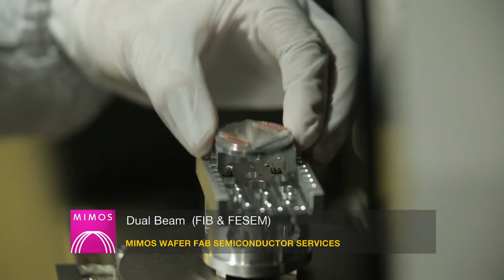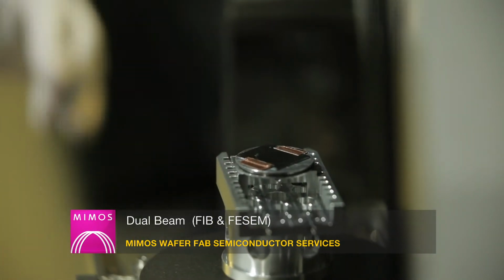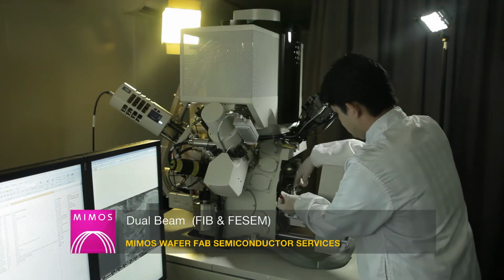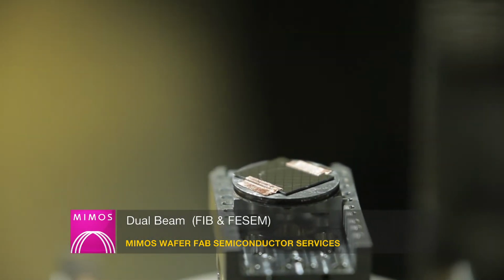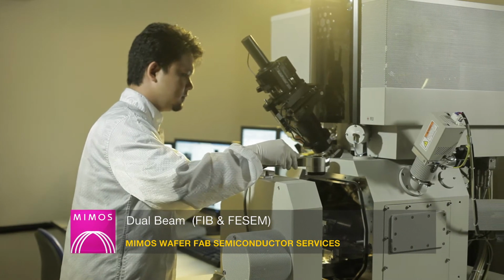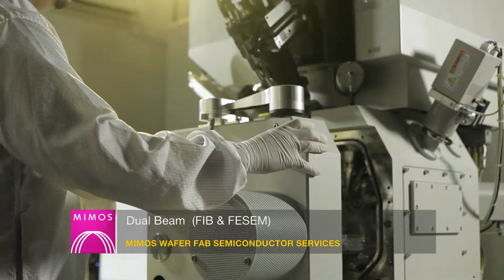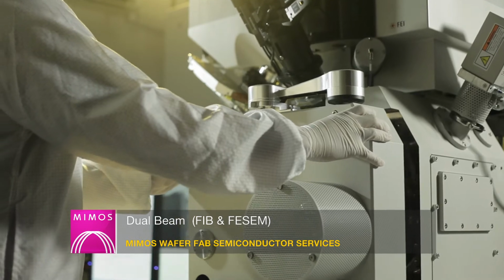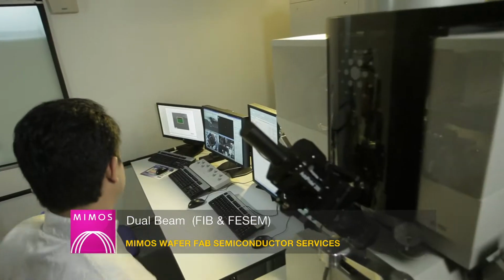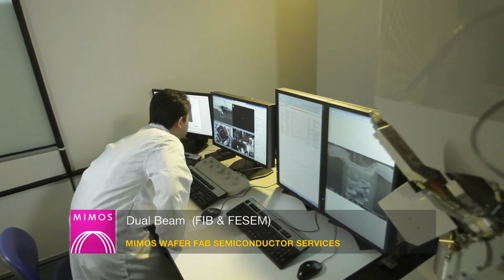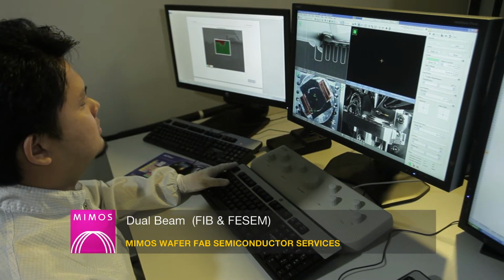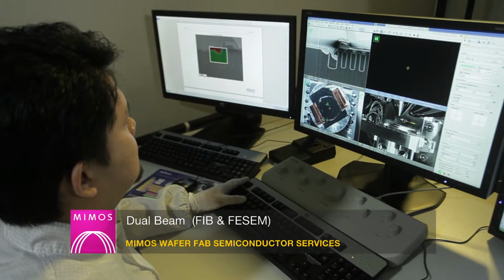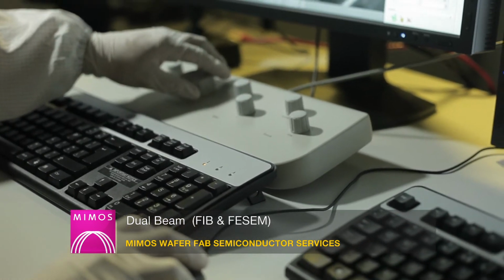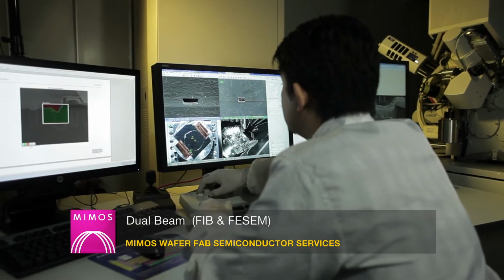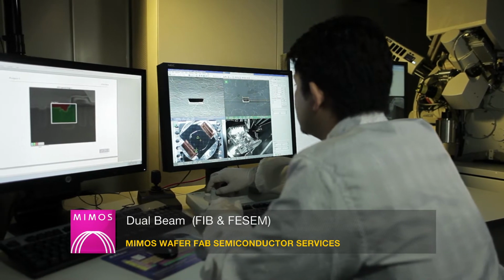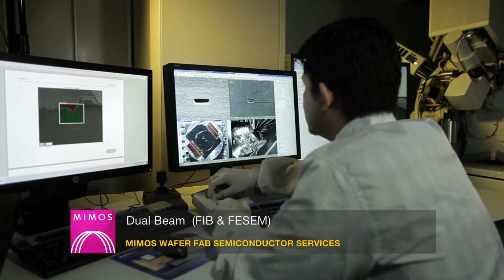The dual beam incorporates both a focused ion beam (FIB) and a scanning electron microscope (SEM) in a single system. The system has the ability to perform precision micro cross-sections of the IC features and deposition of conductor and insulator within nanometer tolerances. Its applications cover opening probe holes, rewiring circuits, device isolation and generating high-resolution images using FESEM.